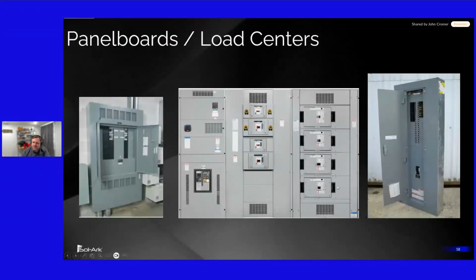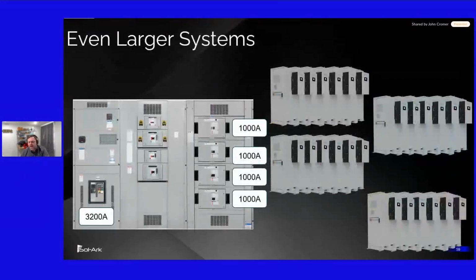When you're looking at these load centers and panel boards, you can subdivide up systems. With 10 Sol-Ark inverters, you'll pass through 1,800 amps of three-phase power, which is good enough for most 2,000 amp panel boards. If you got into a 3,000 or 4,000 amp load bank, you could back up individual groupings off that load center and scale the system as large as you want.